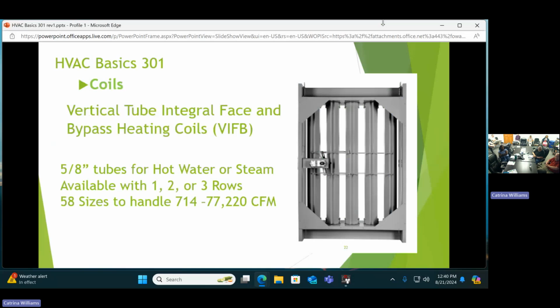They handle both hot water and steam in these cases. These are available in 1, 2, or 3 row models. 58 sizes from 714 to 77,000 CFM. To give you a feel for how big these can get, the height on various sizes, the biggest one can go up almost 12 feet high. And these bundles you see here, the heating elements, up to 12 of those across there. That's how big they can get.